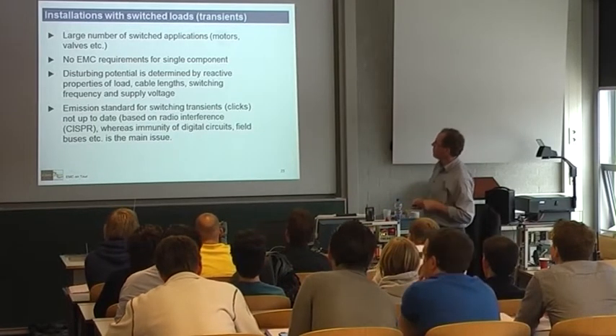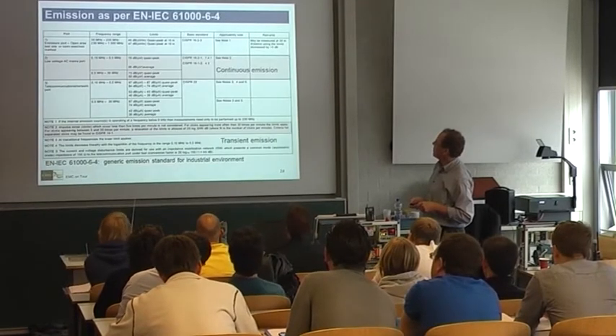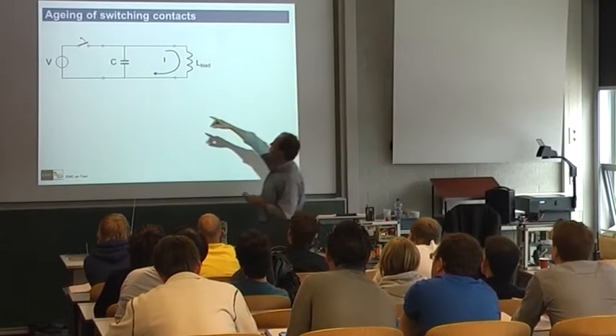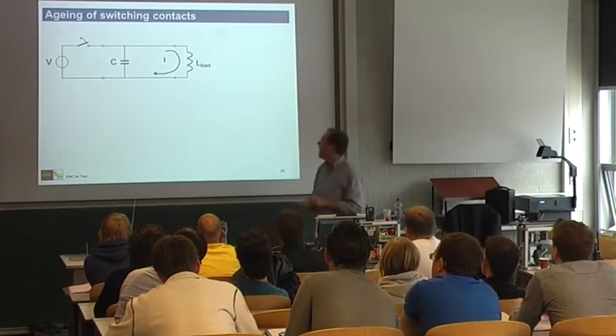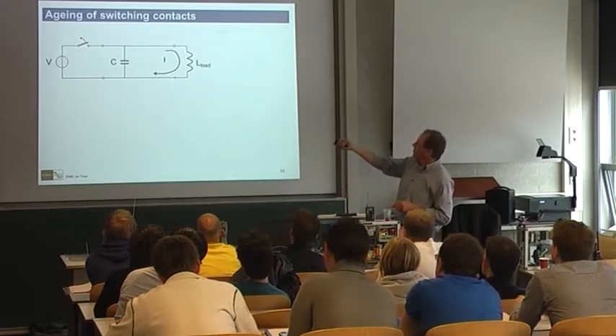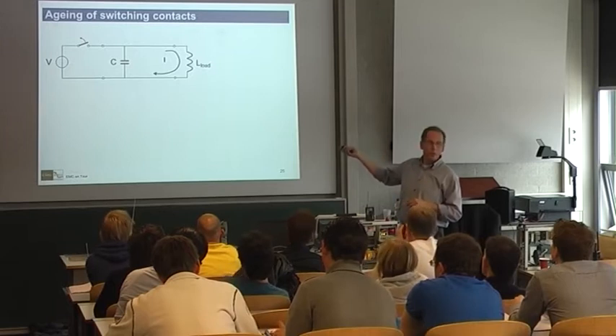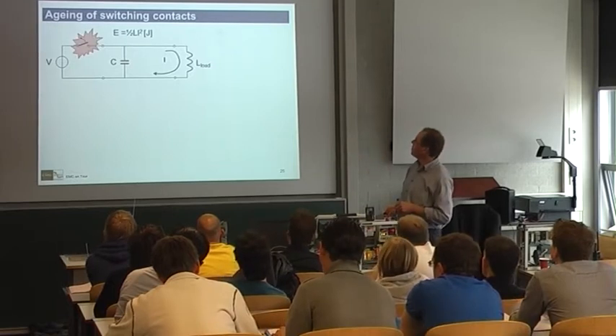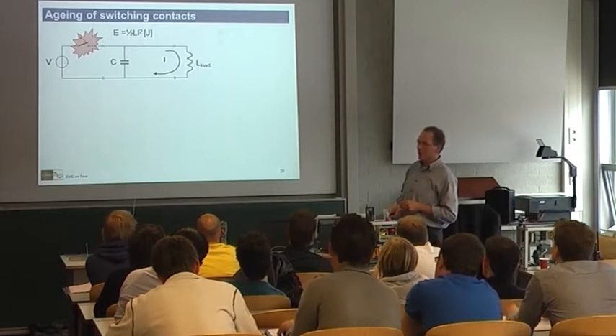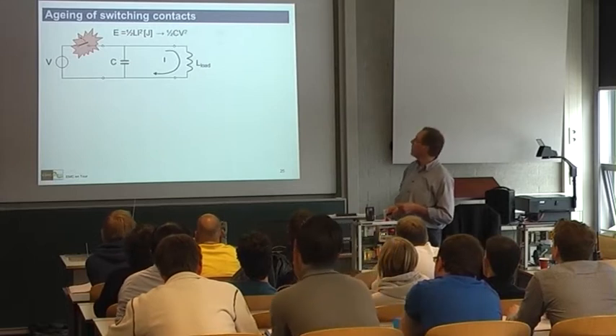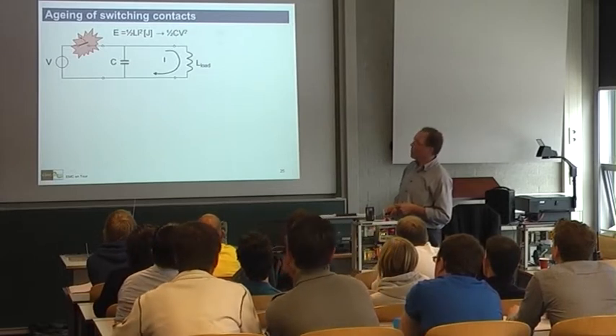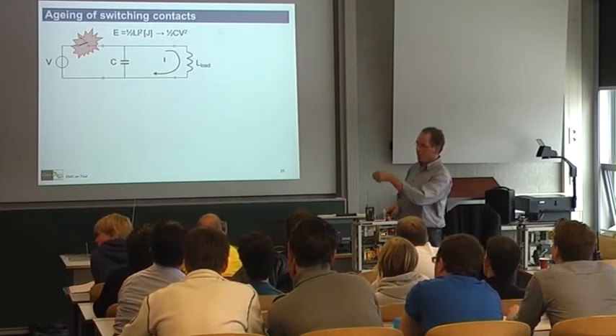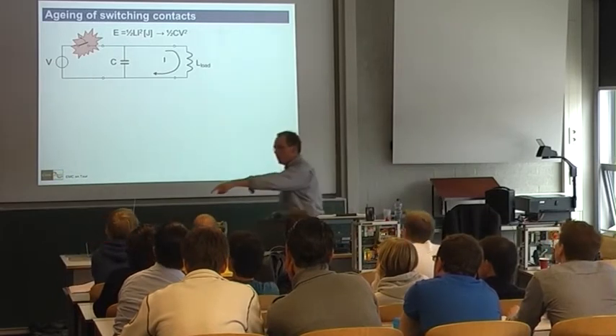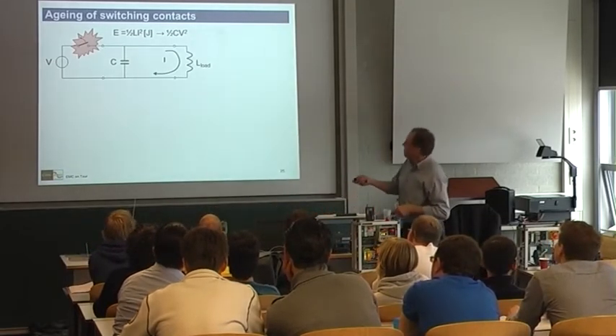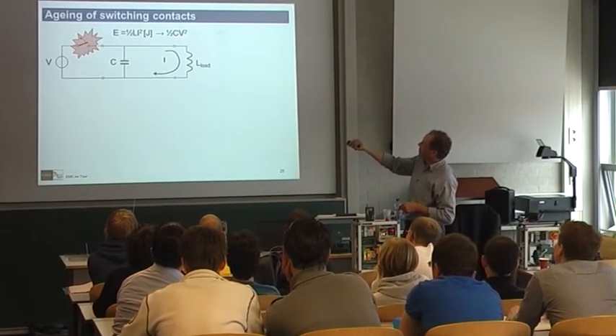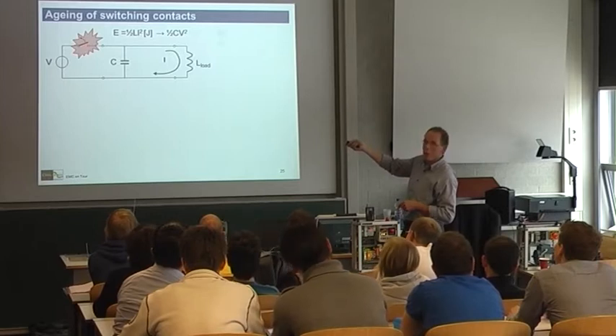Forget about the standards for the moment. What happens is, with the load here and the current in a differential mode circuit, if I disconnect the switch, switching off the valve or the motor, the stored energy, half L i squared, turns into half C V squared, so high voltage - same as with the loop in the ESD experiment. The voltage can go nowhere because it's open circuit, so it builds up across the contacts and produces sparks.